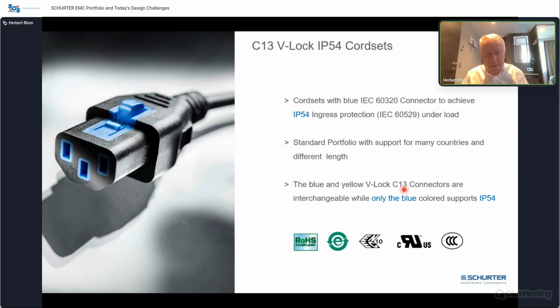We combine this inlet, the waterproofed inlet, with a special V-lock cord set. What is visible is that it is blue, so the cord is black but you have this blue knob and this blue sealing around here. This is a sealed cord set, because only with this cord set can you reach IP54 for the cord connection under load.